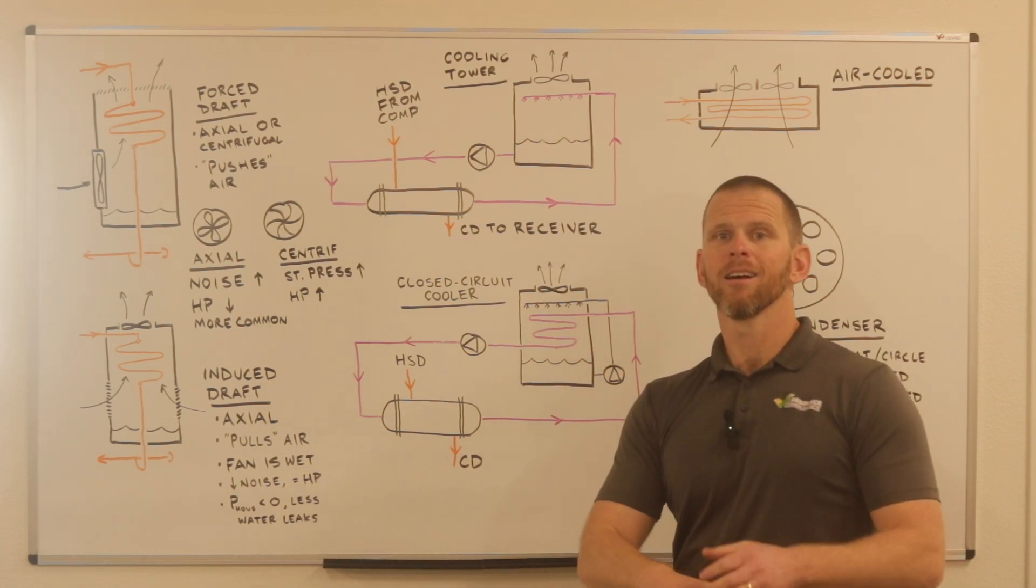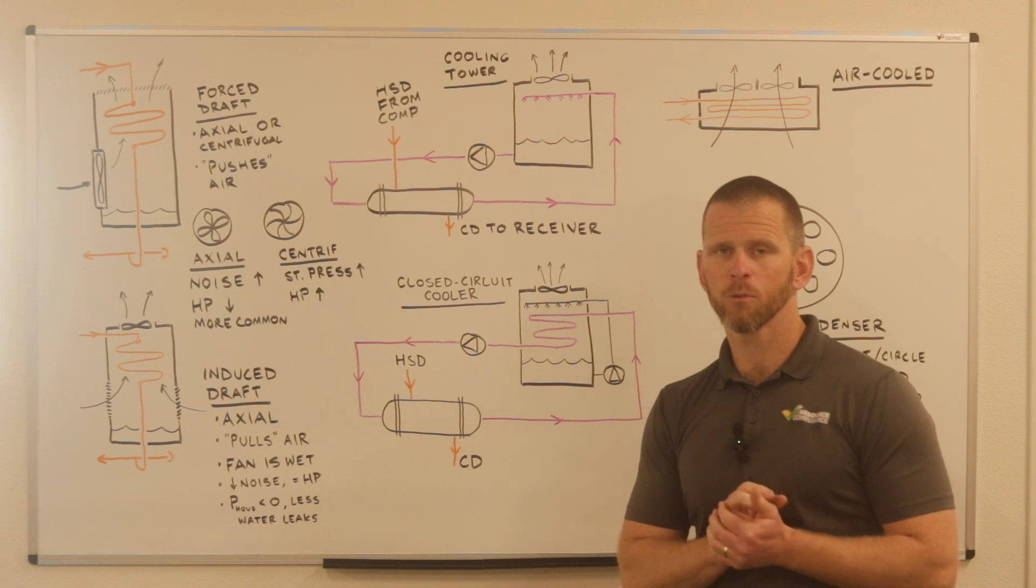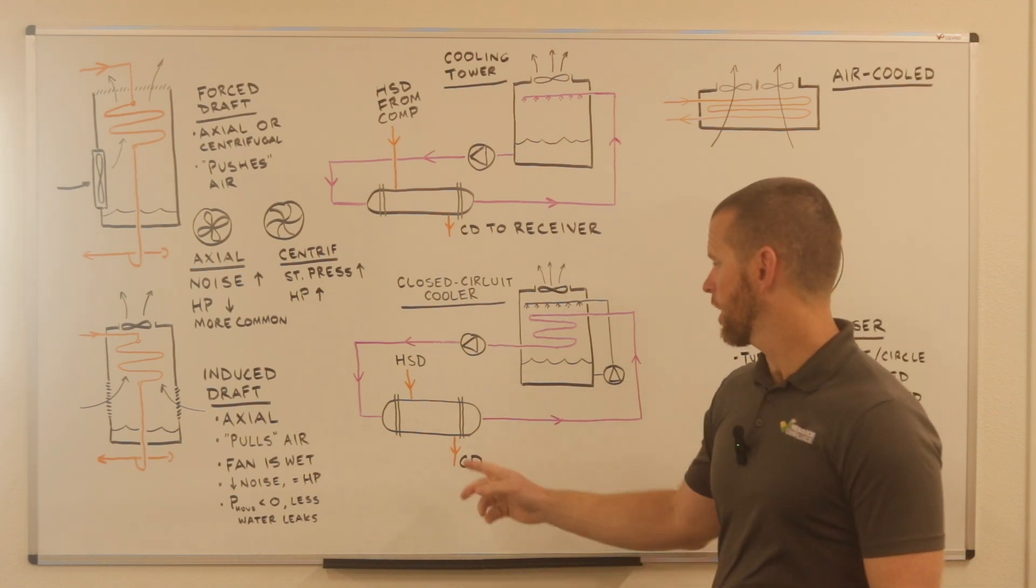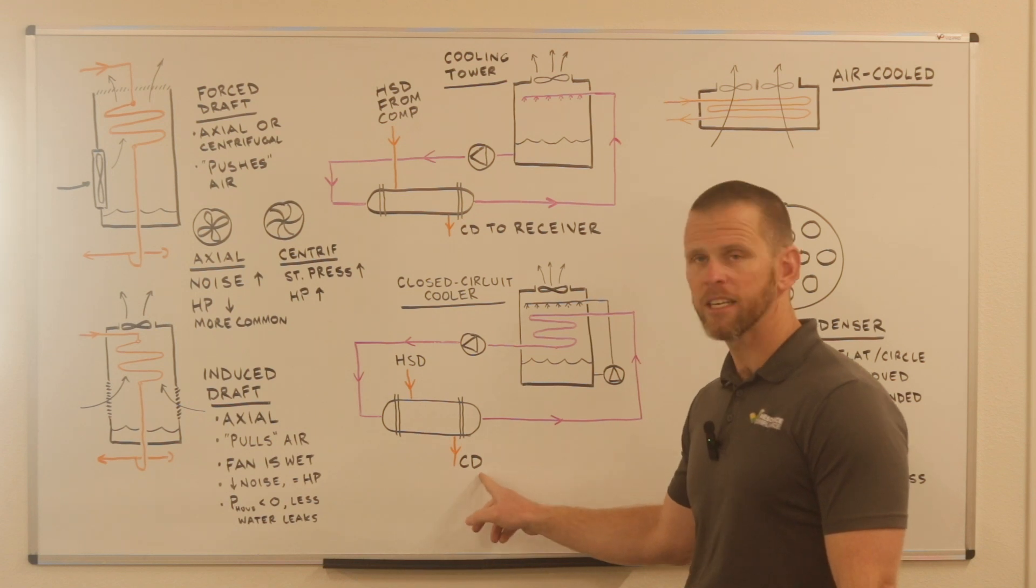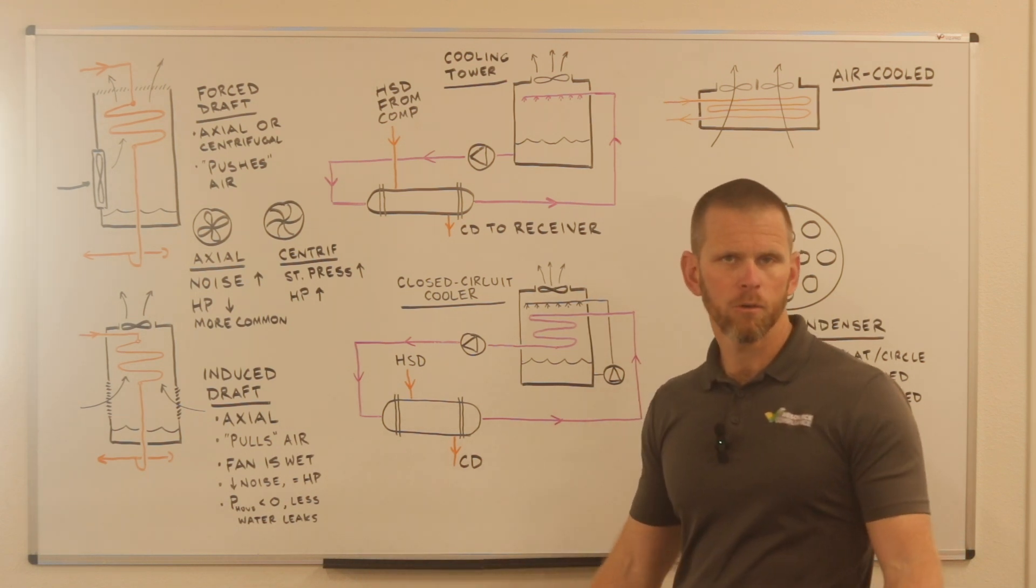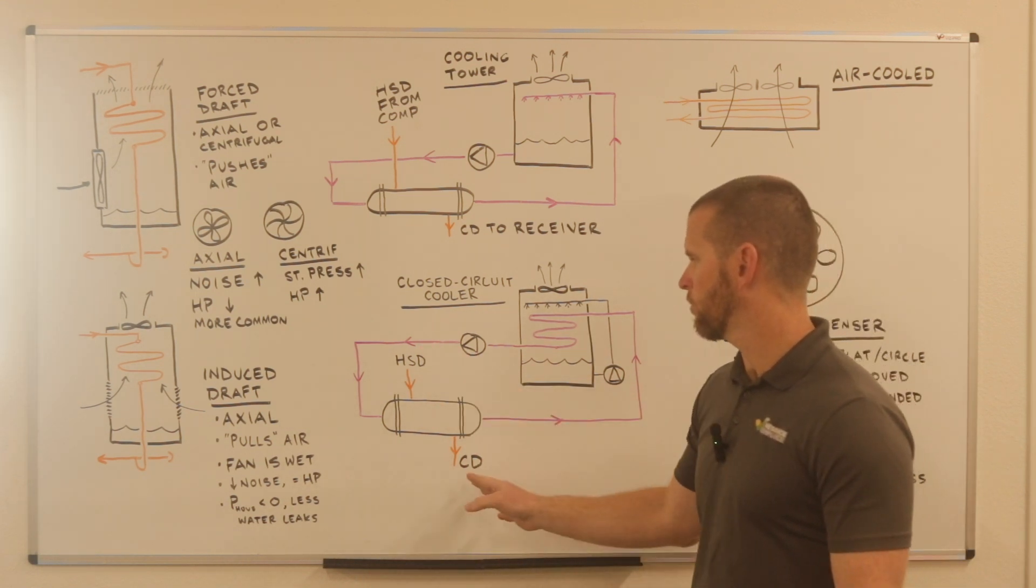Once it hits saturation, all the heat energy that gets rejected is in the form of latent heat, and it causes it to transition from a vapor back to a liquid where it can drain out as condenser drain, and then usually into a high-pressure receiver.